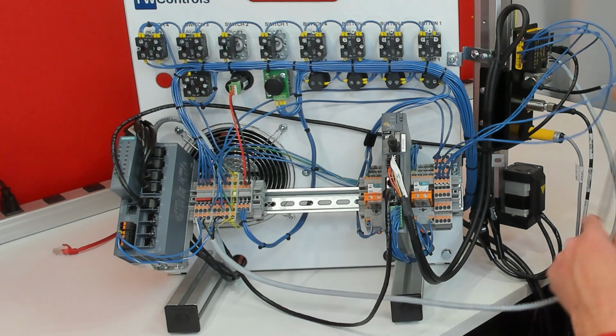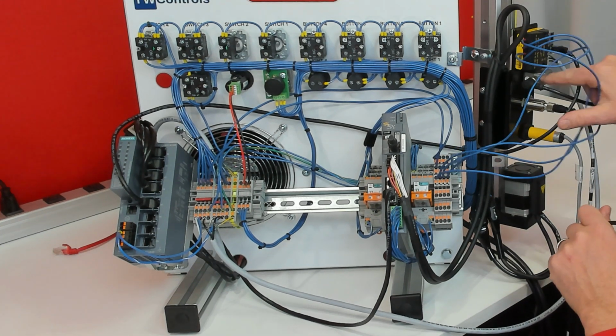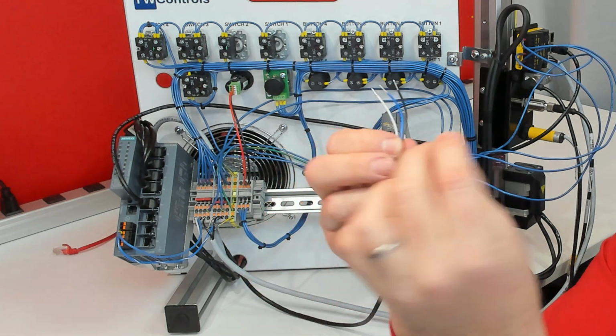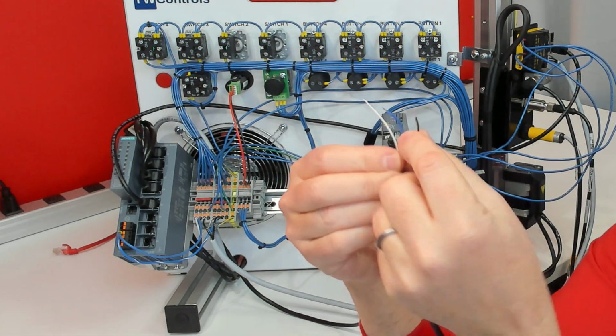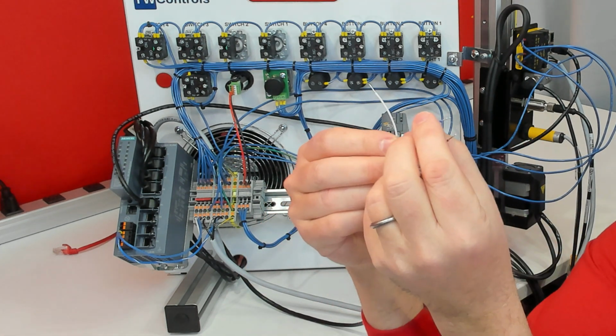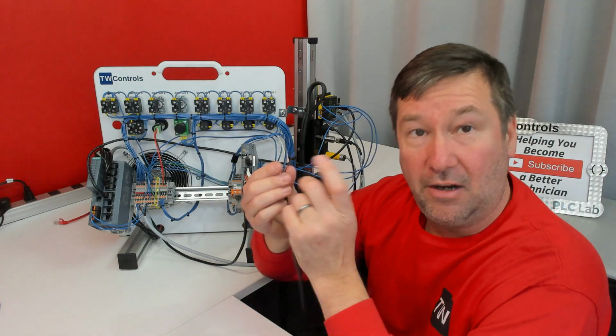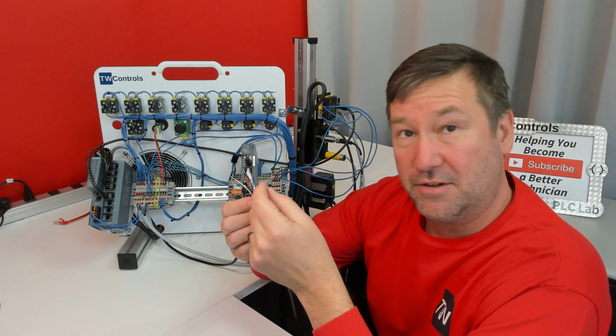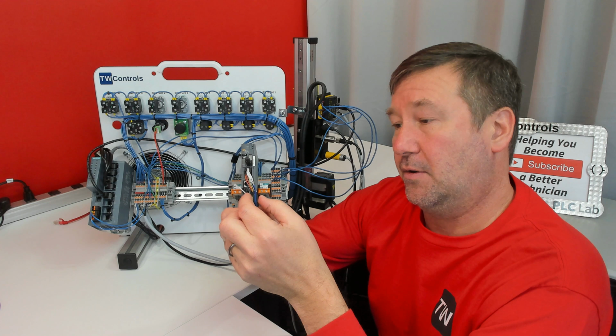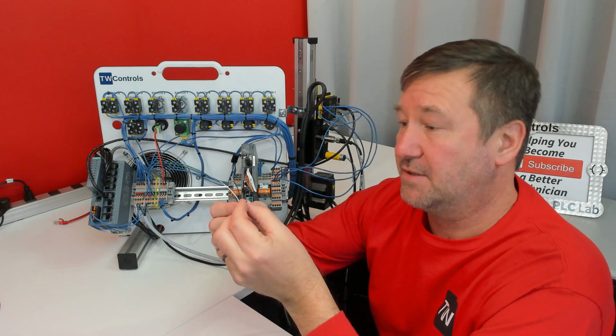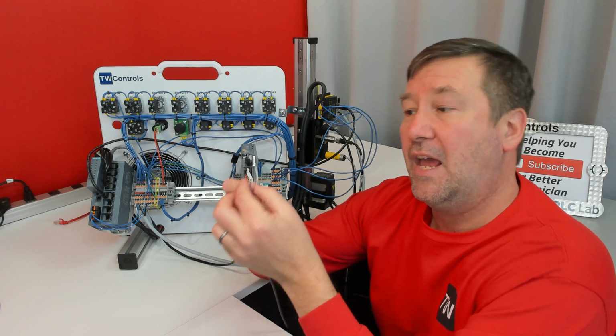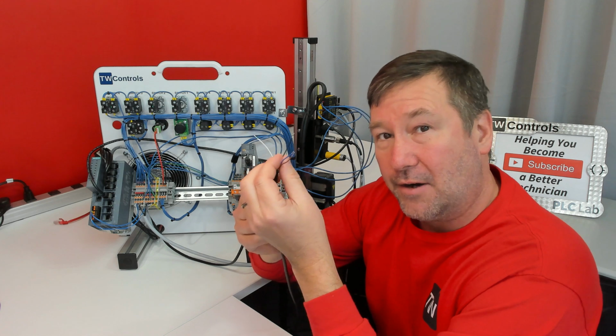And we're going to start with the photoelectric one. That's the top one here. And if we look on it, it's going to have a brown wire, a black wire, a blue wire, and a white wire. And on our getting started wiring diagram, it shows that brown is our plus 24 volt and blue is the minus 24 volt or the 0 volt. And the black wire is the I/O link.